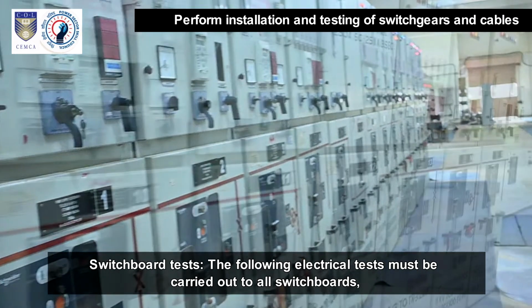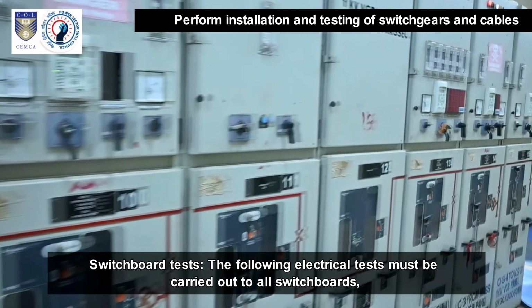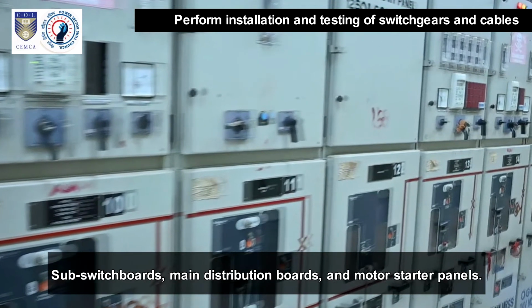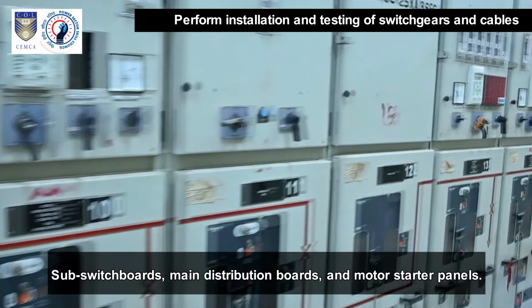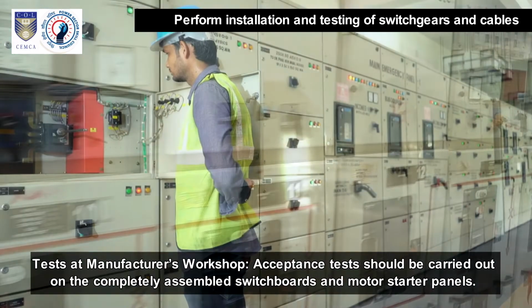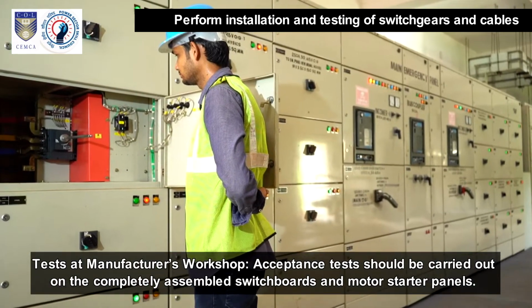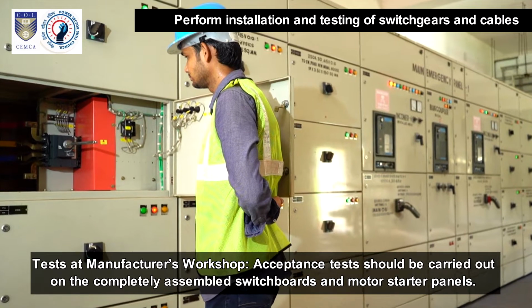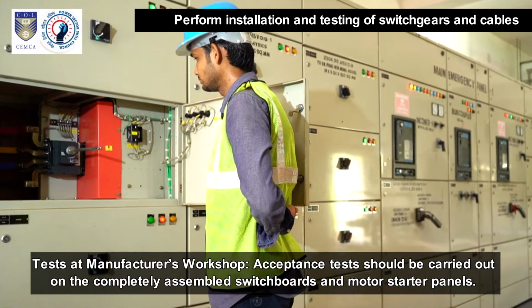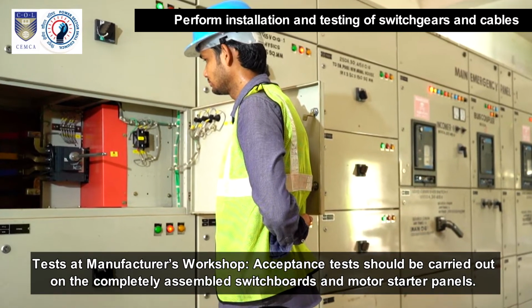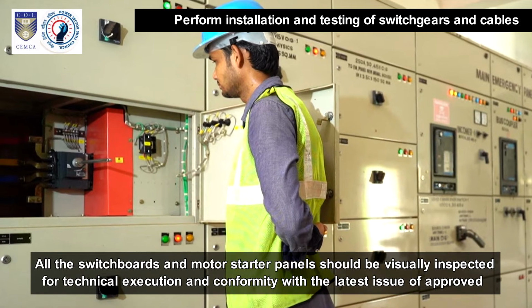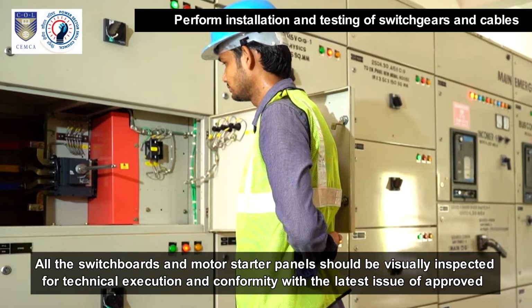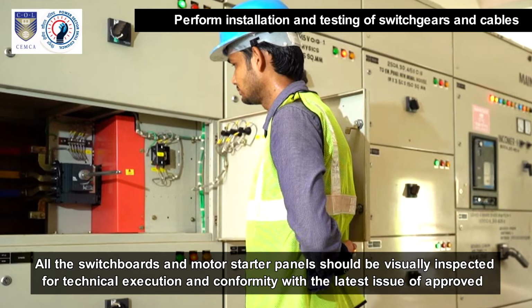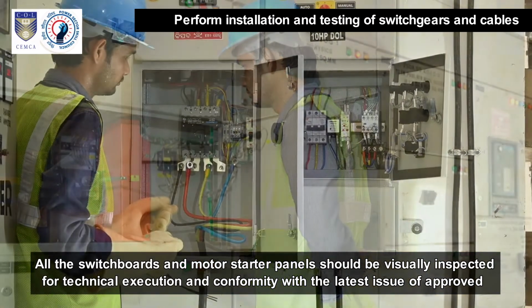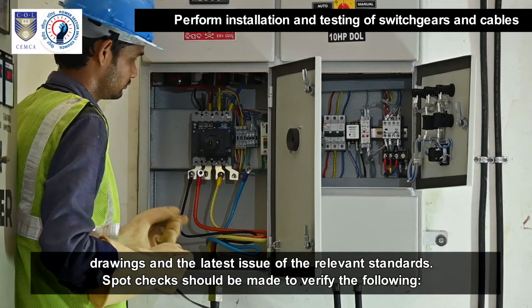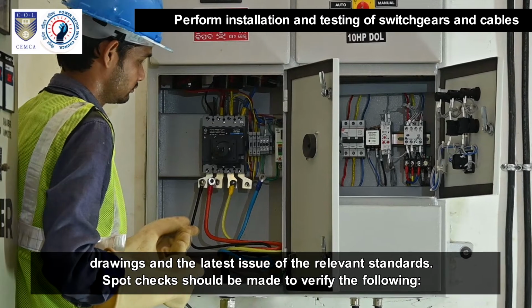Switchboard tests. The following electrical tests must be carried out to all switchboards, sub-switchboards, main distribution boards, and motor starter panels. Tests at manufacturer's workshop. Acceptance tests should be carried out on the completely assembled switchboards and motor starter panels. All the switchboards and motor starter panels should be visually inspected for technical execution and conformity with the latest issue of approved drawings and the latest issue of the relevant standards.